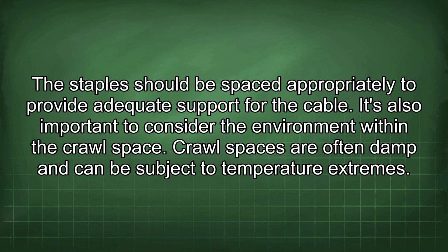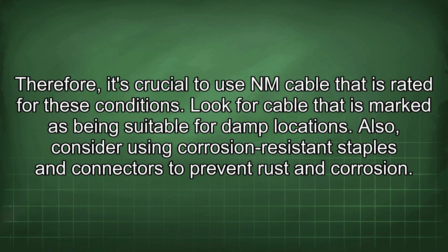It's also important to consider the environment within the crawl space. Crawl spaces are often damp and can be subject to temperature extremes. Therefore, it's crucial to use an NM cable that is rated for these conditions. Look for cable that is marked as being suitable for damp locations. Also, consider using corrosion-resistant staples and connectors to prevent rust and corrosion.